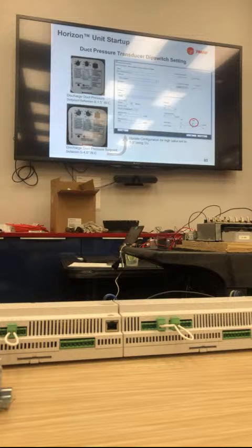Sorry, we've only seen a VAPI controller. Is this the same thing? This one's coming. It's a newer one. We made this change in November. The other model is extinct. This is the new VAPI that's going to replace the old one. Yes, it's the same form, fit, function pretty much. It's just got different dip switch settings. It is a VAPI sensor. It's the same one, just their newer model. And then also, I've had a couple of those fail.